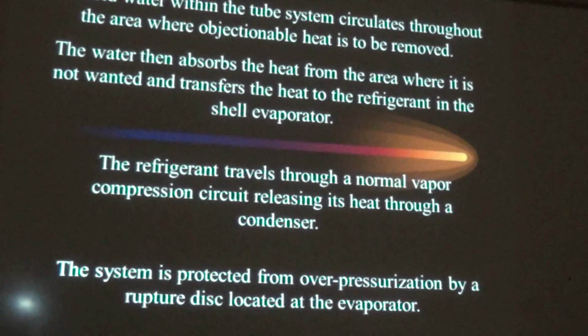How it works: cold water. Remember, water is our secondary refrigerant. Cold water within the tube system circulates throughout the area where the heat is to be absorbed. The water then absorbs that heat from the area, this room, where we want it, not want it, and it transfers the heat to the refrigerant in the shell evaporator. The refrigerant travels through a normal vapor compression circuit, releasing the heat through a condenser. The system is protected from overpressurization by a rupture disc located at the evaporator.